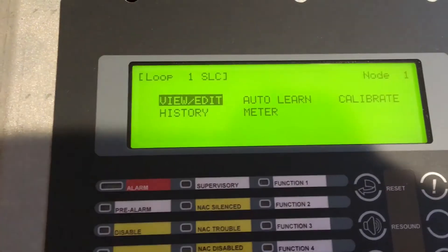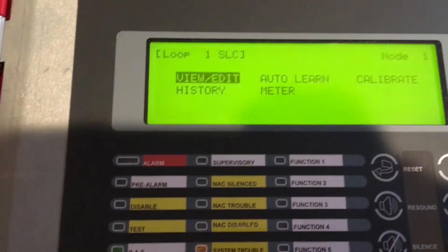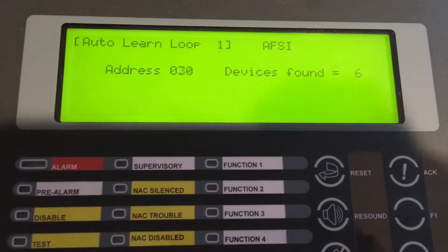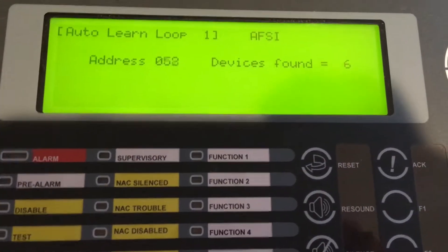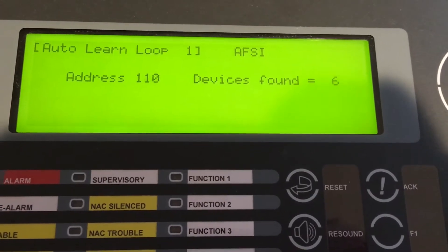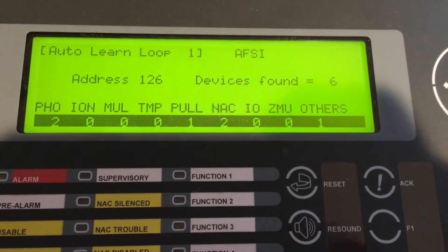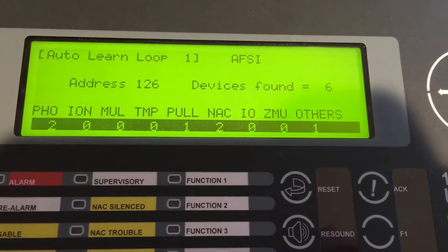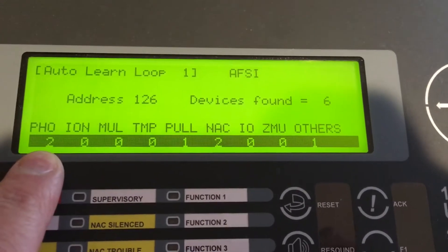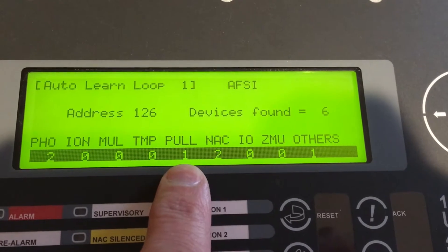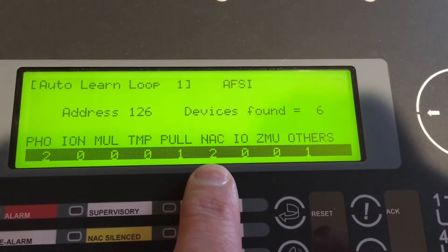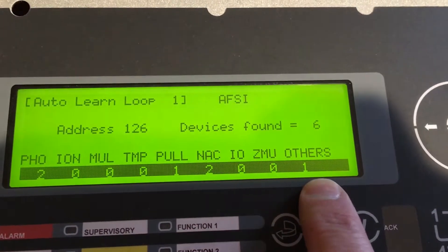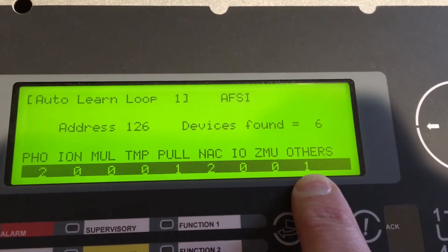We're going to choose auto learn or the 2 button. What the panel is going to do is go through every single possible address on the system, looking at those addresses to see if there is a valid response. When it gets to the end of the list, it'll give us a summation. It's found two smoke detectors, a pull station, two NAC modules which are these two new carbon monoxide detectors, and one other device which will be the monitor module we added to the system.